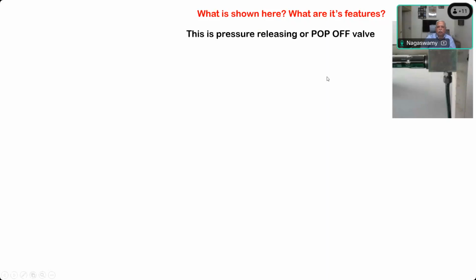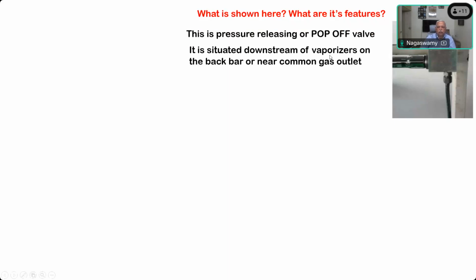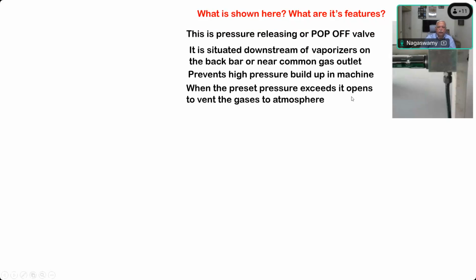This is called the pressure releasing or pop-off valve, present on the back bar, situated downstream of the vaporizers or near the common gas outlet. It prevents high pressure buildup inside the machine, and when the preset pressure is exceeded, it opens to vent the gases to the atmosphere.